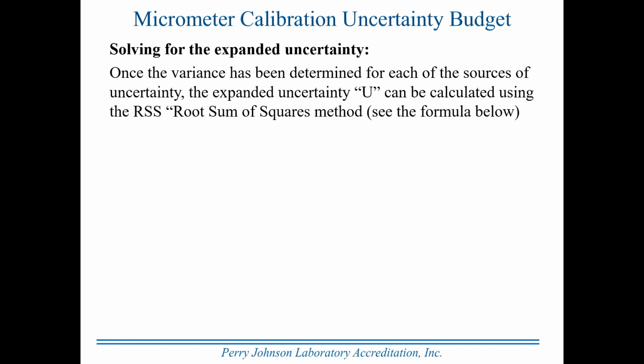Solving for the expanded uncertainty. Once the variance has been determined for each of the sources of uncertainty, the expanded uncertainty, capital U, can be calculated using the RSS, root sum of squares method. Sometimes you'll hear this as taken in quadrature. Older mathematicians tend to talk like that. We refer to it as the root sum of squares. Remember, we had taken the standard uncertainty multiplied by the coefficient of sensitivity, got that product, squared that product for each one of these 6. Now what this is saying is you sum all those squares. In other words, you take the variances and add them together, and you'll see the formula below, the root sum of squares. This is the compressed shorthand version of the equation.